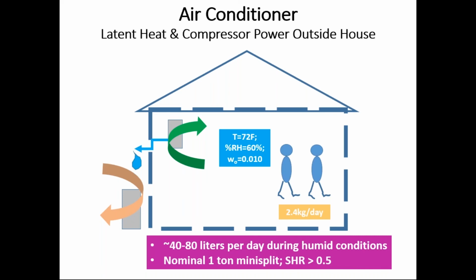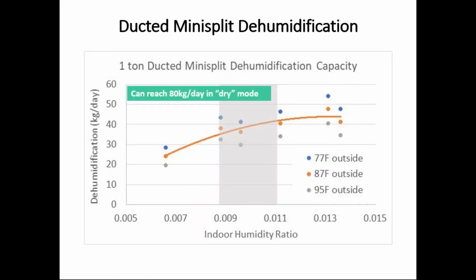But many of the homes that we're dealing with, high performance, progressive builder based homes, 1 to 1.5 tons of cooling and heating seems to be managing pretty reasonably sized homes with good occupancy. So your typical 1-ton air conditioner of a mini split type heat pump, somewhere around 40 to 80 liters per day. This is data from one manufacturer, and it changes with the indoor humidity ratio.